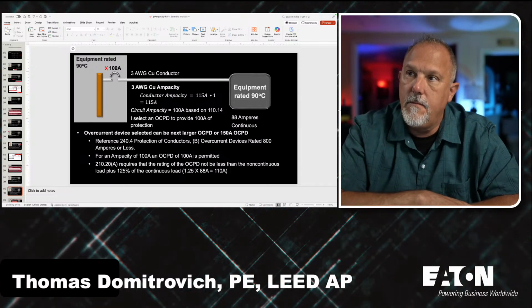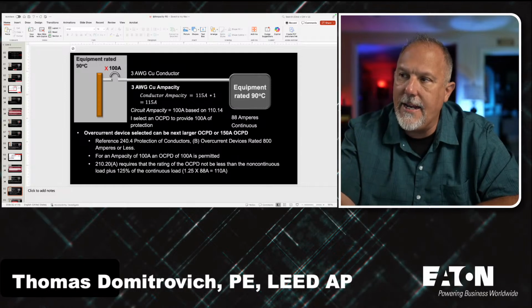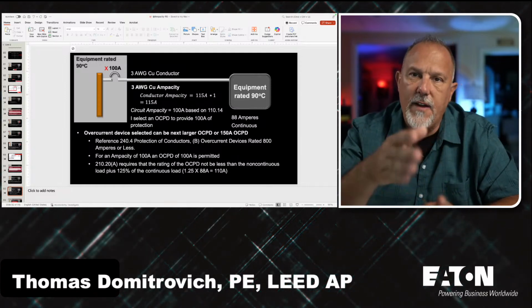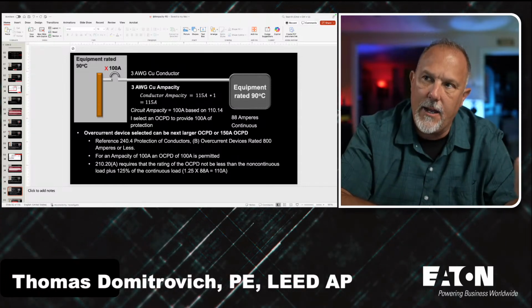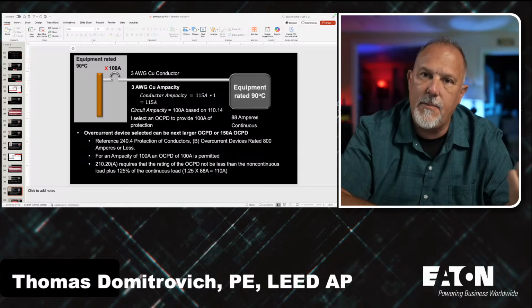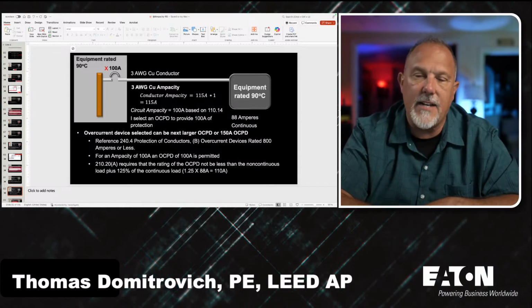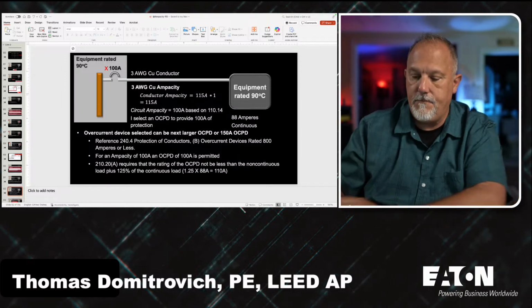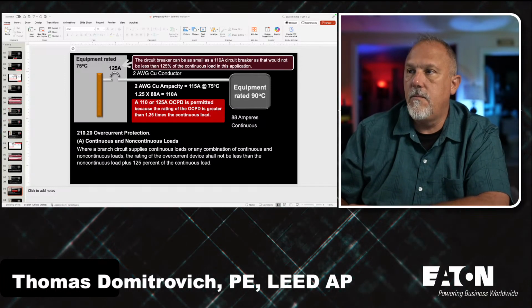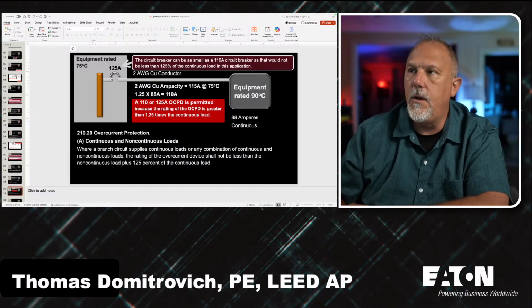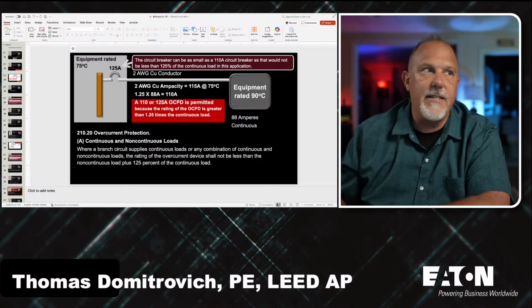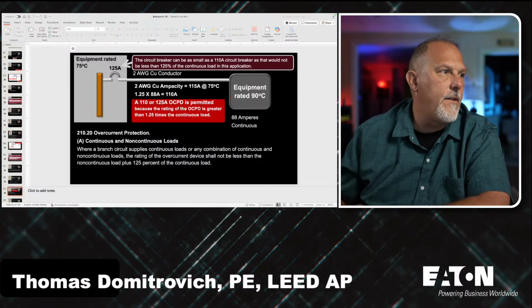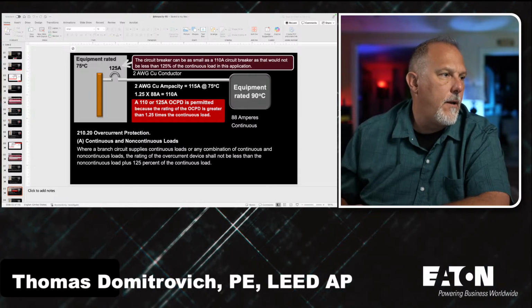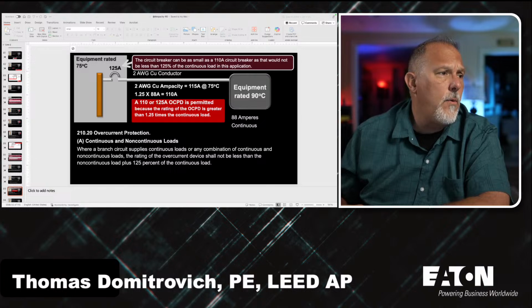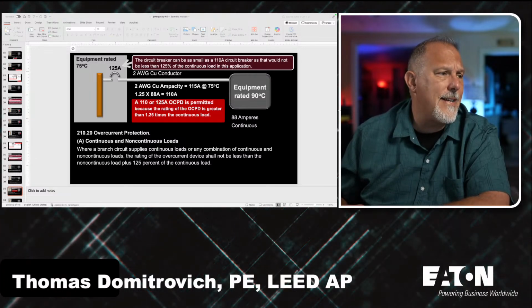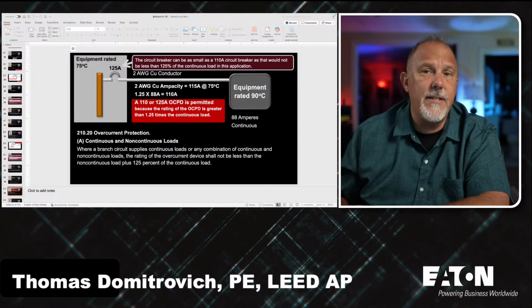The reason I can't is because I have 88 amps of continuous current. I need to take 1.25 times that continuous current, then select my overcurrent device. My overcurrent device has to be greater than or equal to that number. In this case, I have a 100 amp breaker, so I can't do it. So what do I do? I go to the next standard size, and I go to Article 240 for the standard size breakers. 240.6. I had 100 amp. I could go to 110.